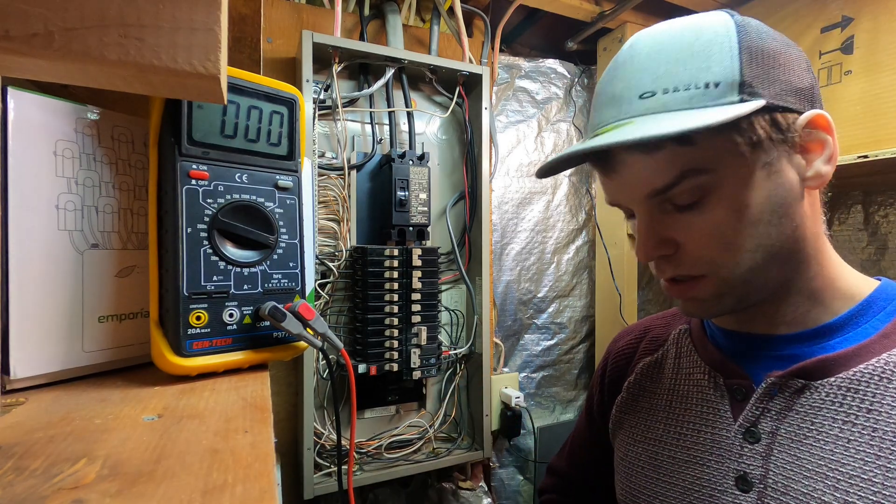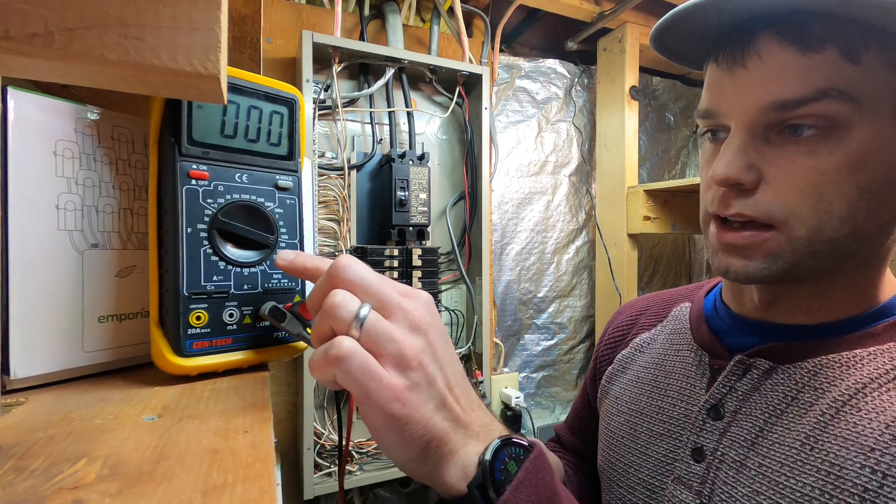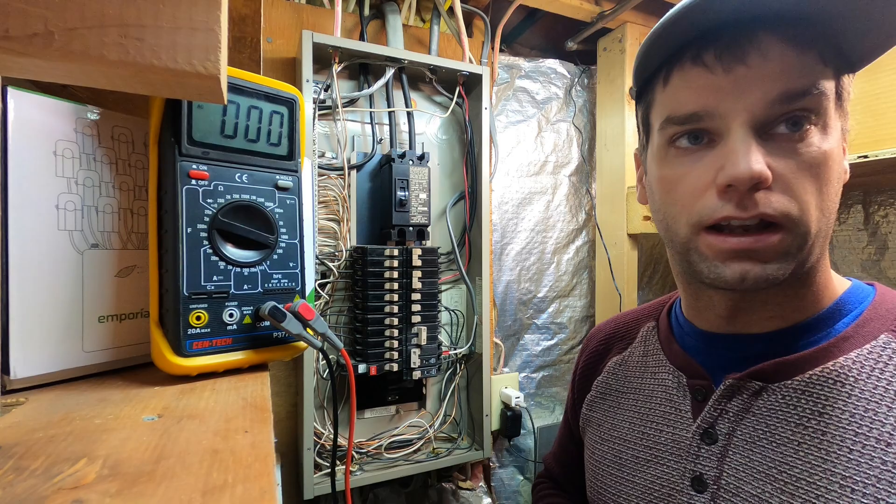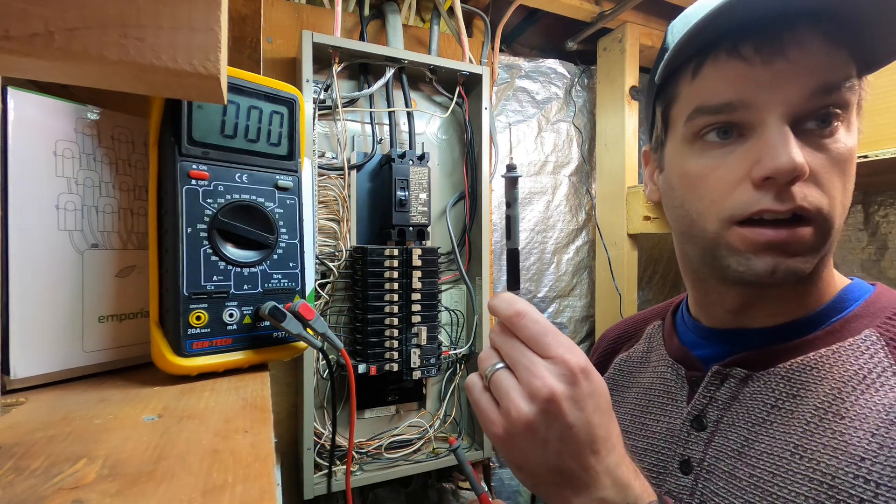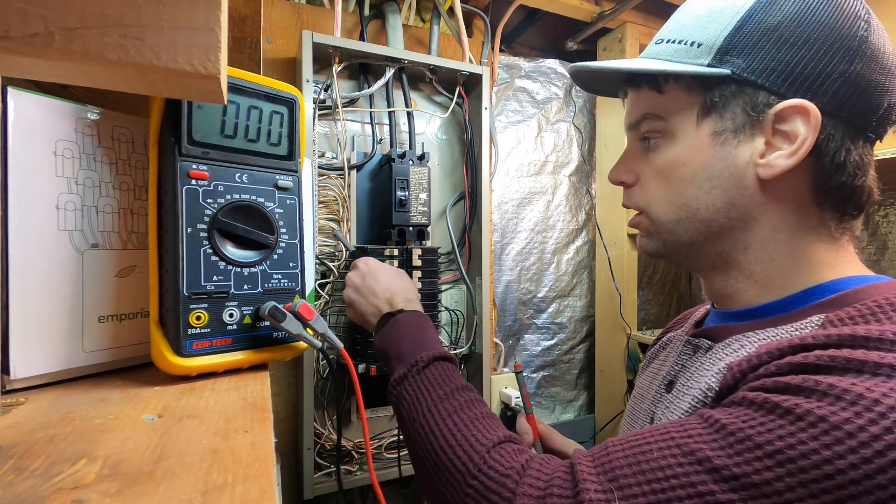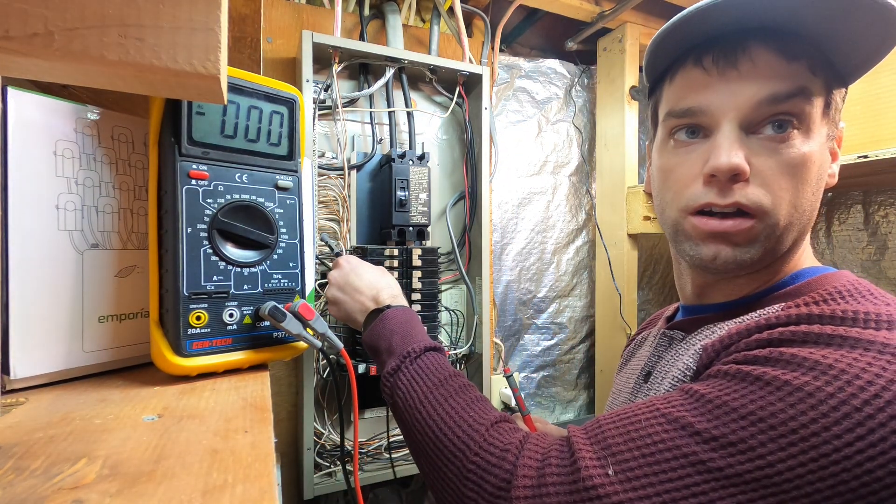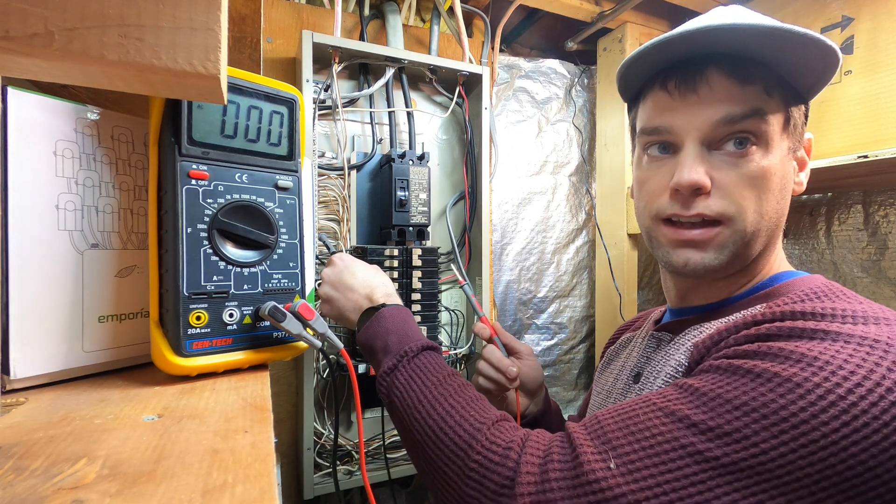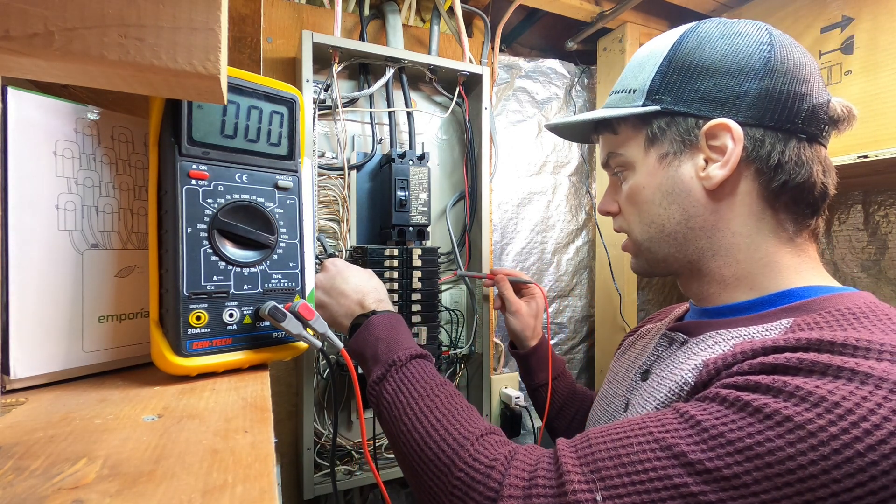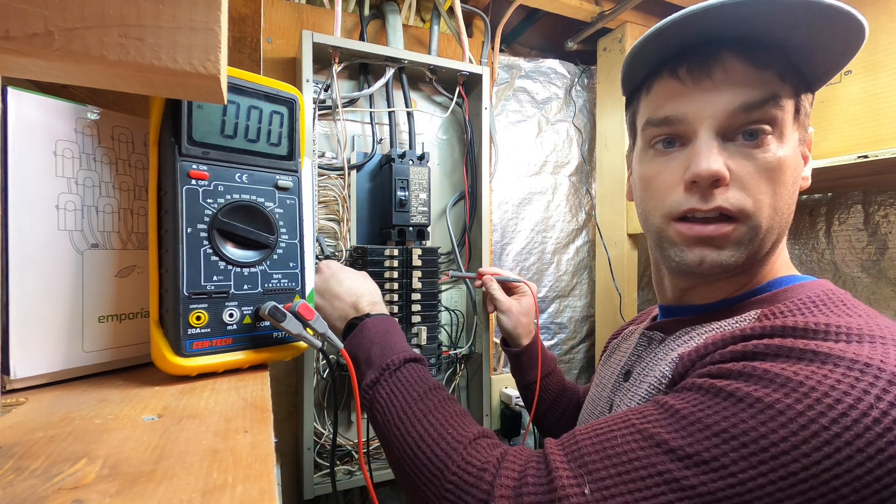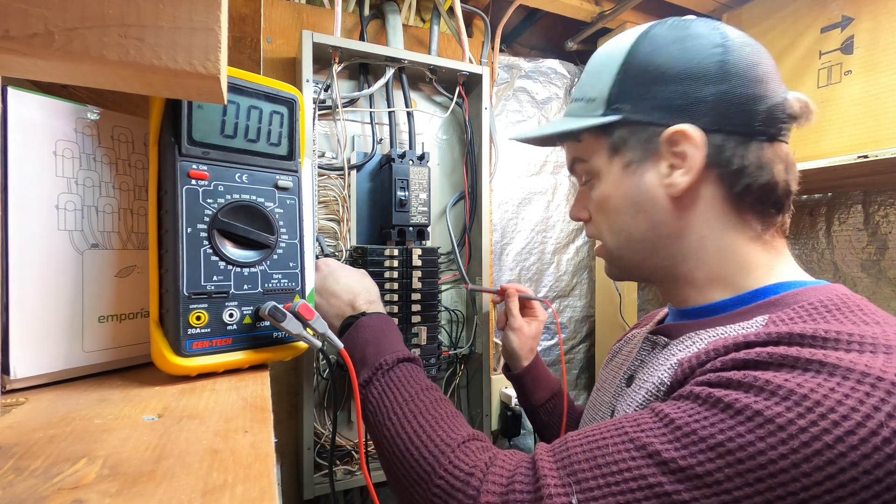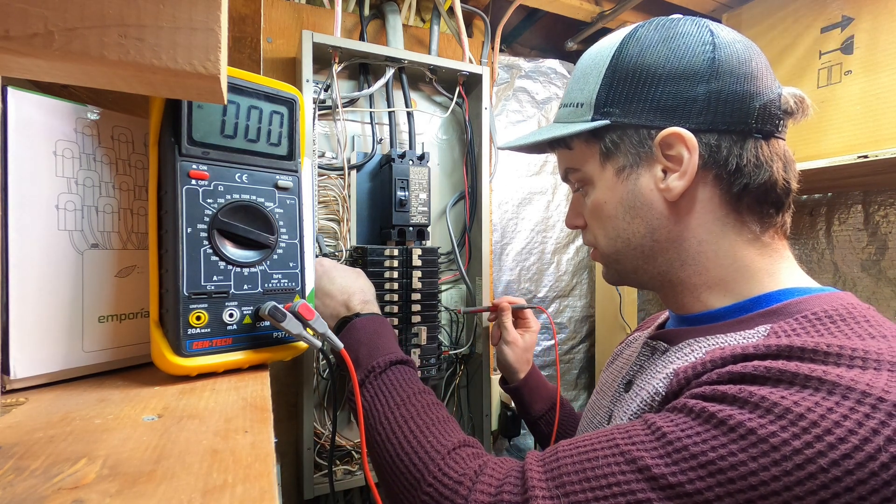So what we're going to do is we're going to take our multimeter. You can see I've got it set to 700 volts, the high volt setting for this. We're going to take our black negative lead, put it on our ground and neutral bar. Since this is a main panel, ground and neutral are together. And we're going to take and just check against a screw on a few of these. And you can see zero volts, zero volts, zero volts.